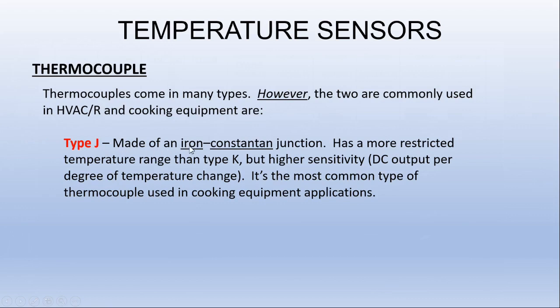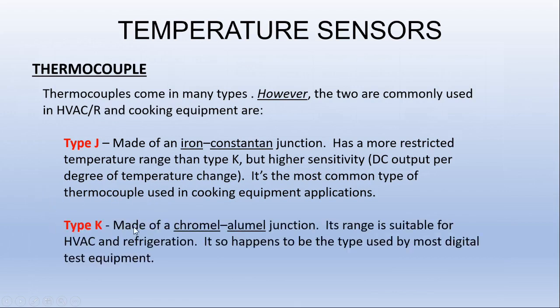It's made of an iron Constantan junction, has a more restricted temperature range than a type K, but higher sensitivity, which means a DC output per degree of temperature change. It's the most common type of thermocouple used in cooking equipment applications. The type K is made of a chromel-alumel junction. Its range is suitable for HVAC and refrigeration. It so happens to be the type used by most digital test equipment as well.